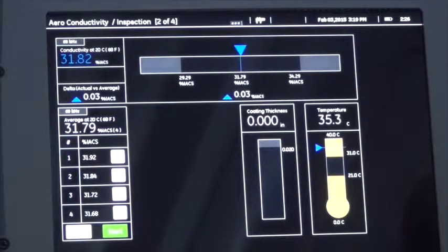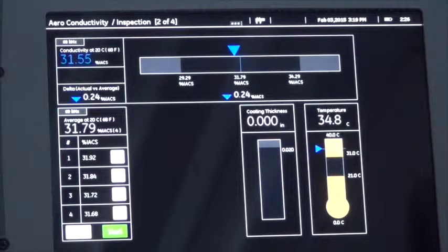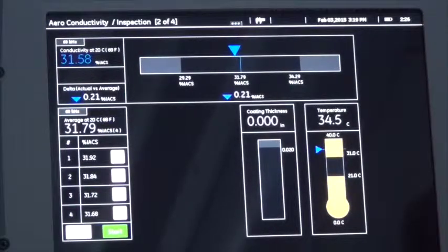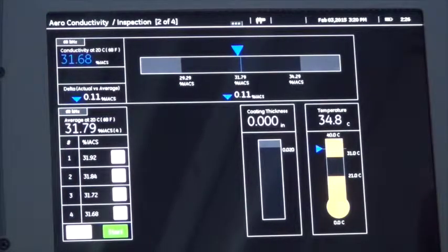So one hint, when you have an environment where the temperature of the probe may be changing rapidly due to changes in temperature of the material, rather than keeping the probe in continuous contact with the material, take a reading, pick it up into air, put it back down on the material.